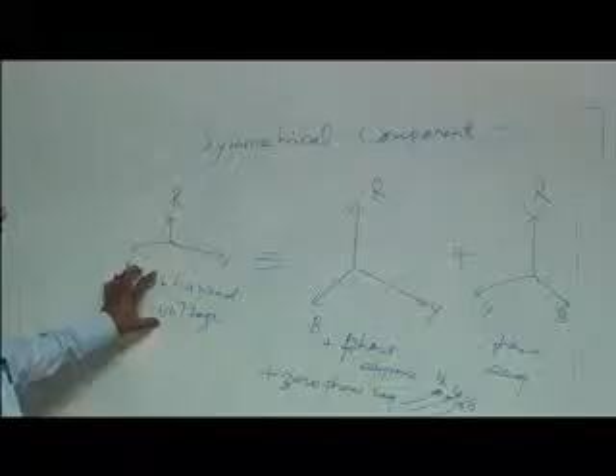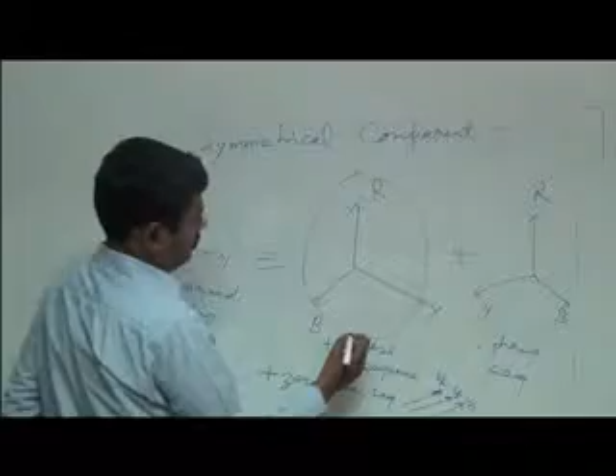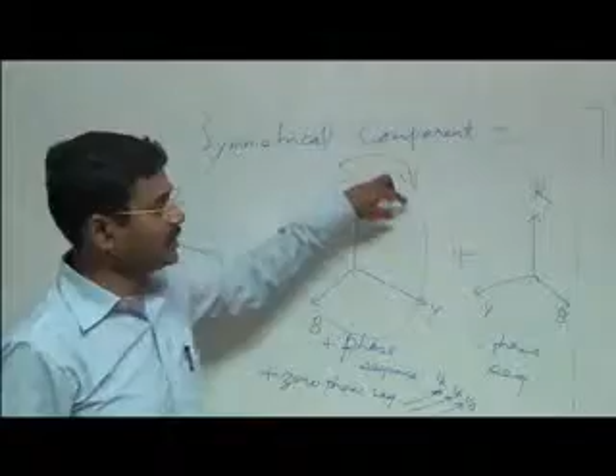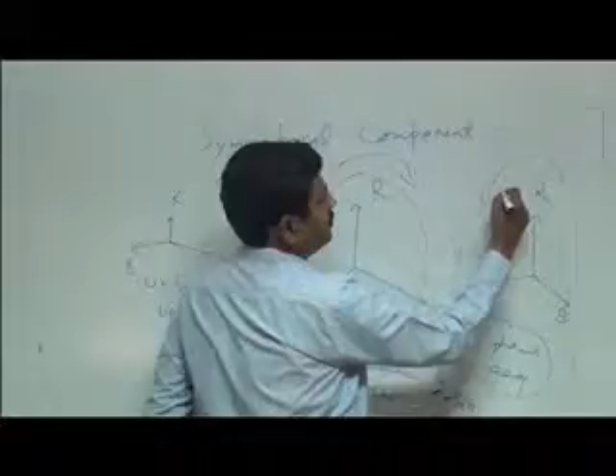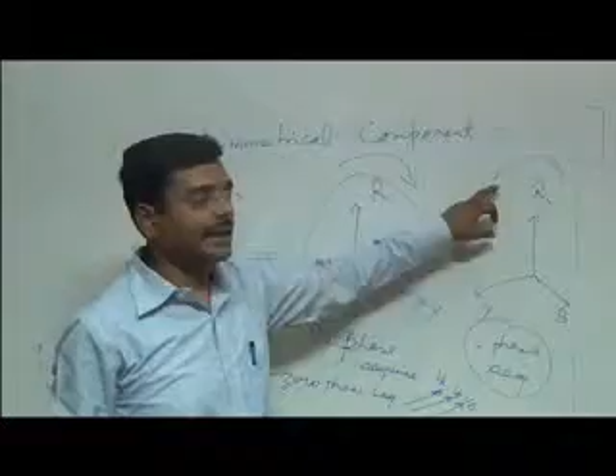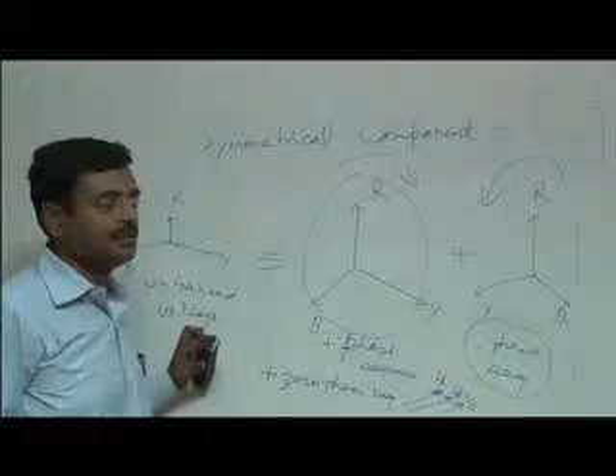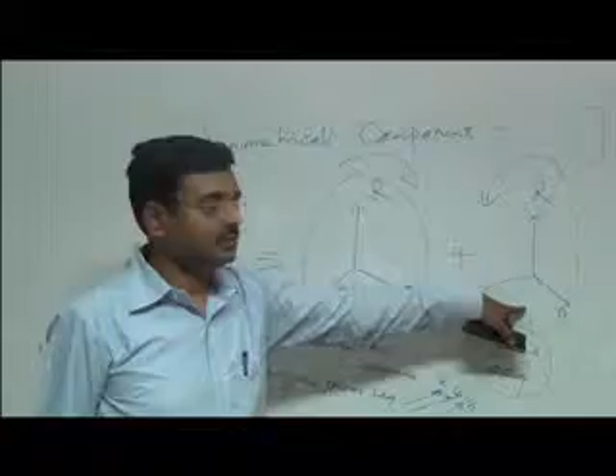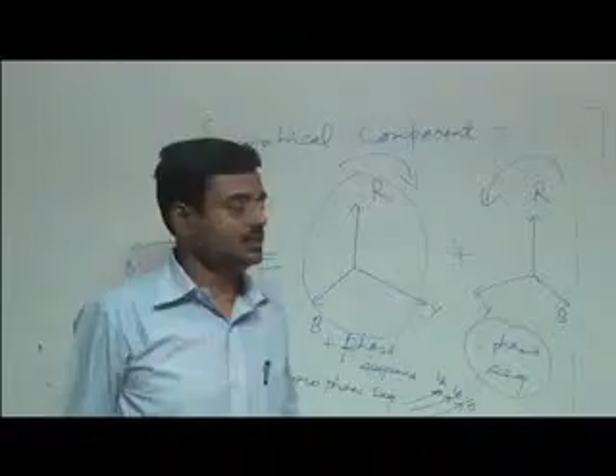So in case of unbalanced voltage, there will be a positive sequence voltage, negative sequence voltage, and zero phase sequence voltage. And what are the repercussions? The positive sequence will produce a rotating magnetic field which is clockwise, and because of negative phase sequence there will be a negative rotating magnetic field and it will produce a negative torque. Since there is no 120 degree phase displacement in zero sequence, it will not produce any rotating magnetic field and it will contribute to the I-square losses. So because of unbalancing in voltage, a negative torque and I-square losses have come into our system.